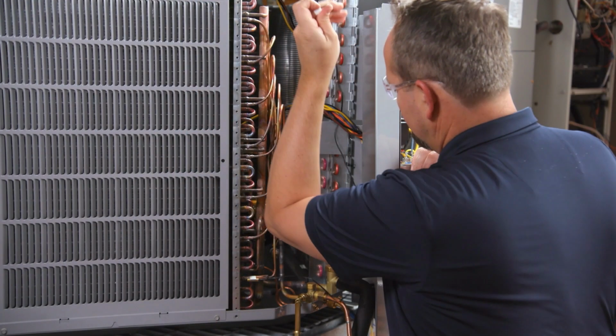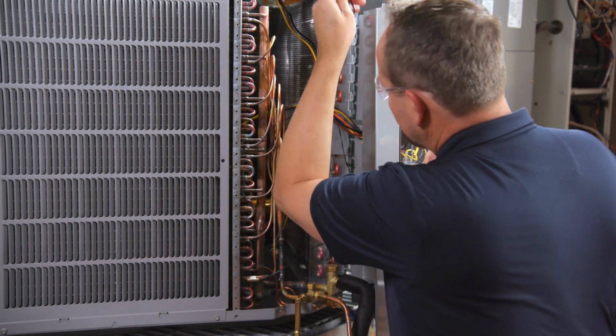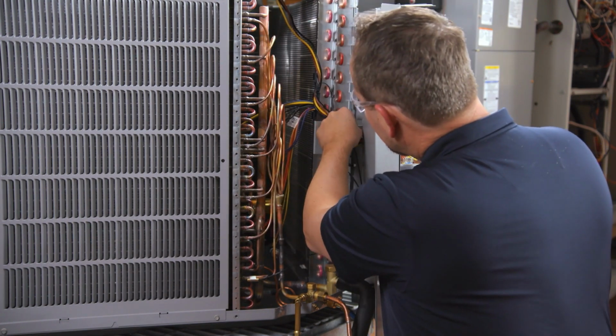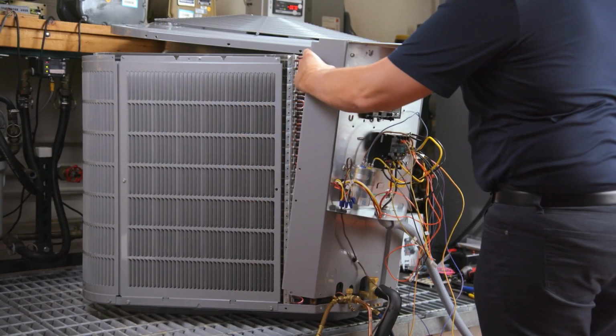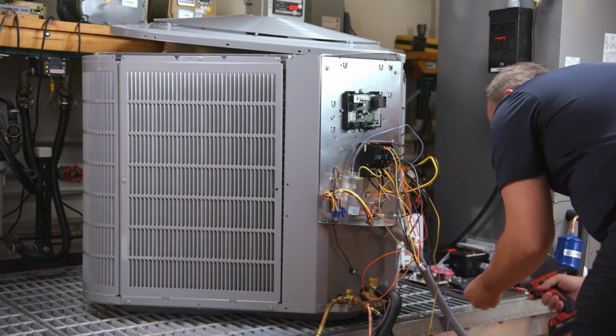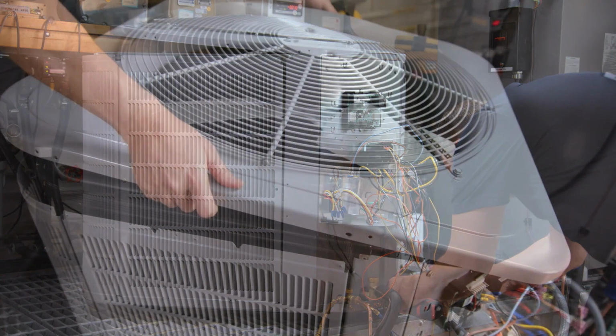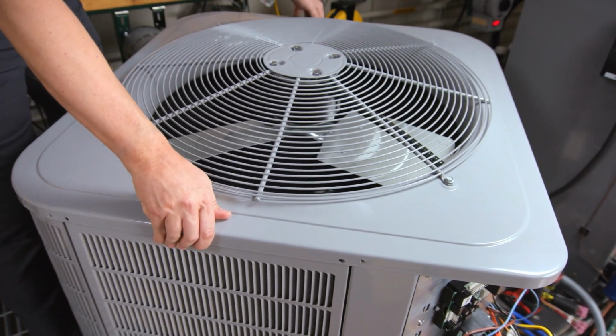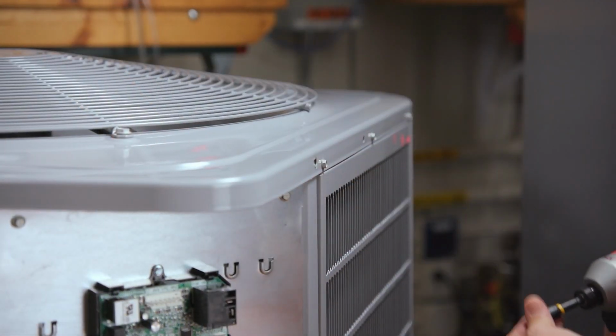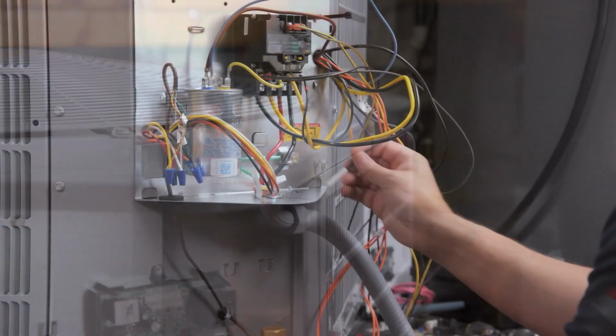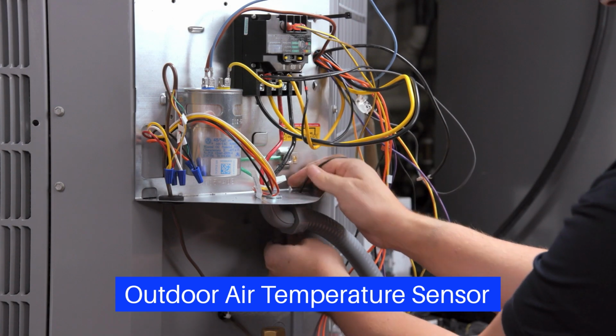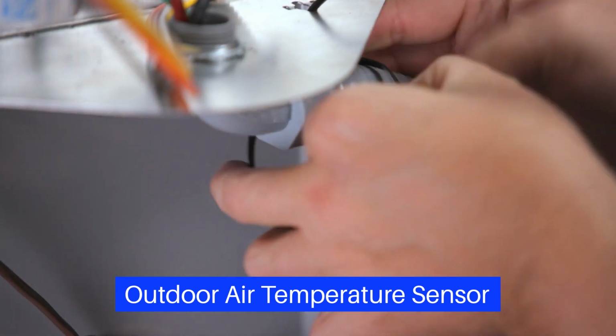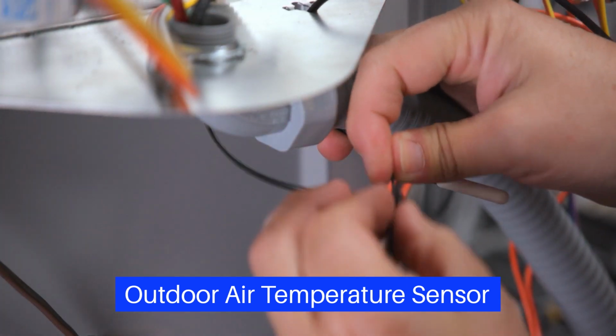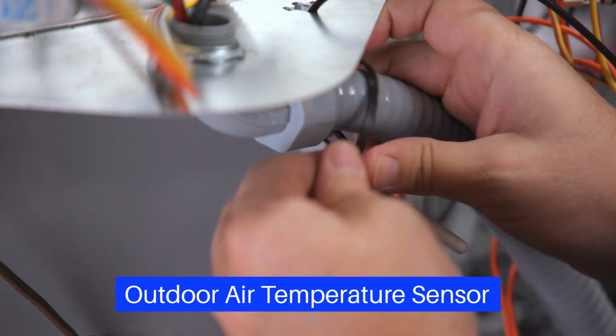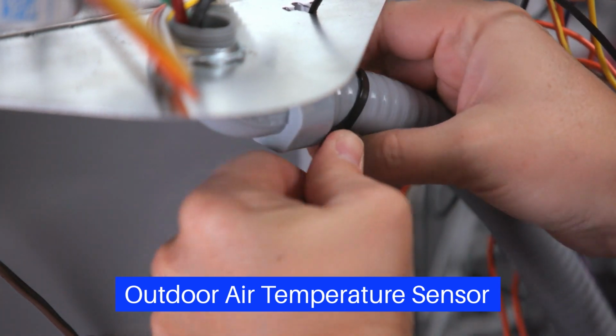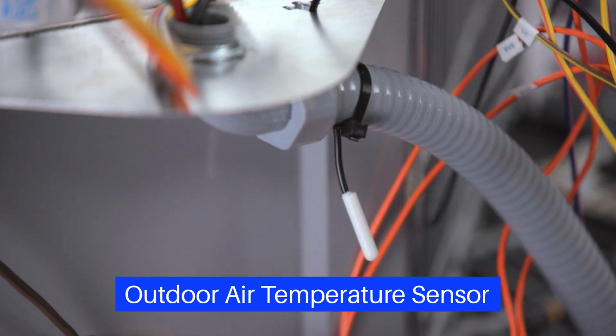Route the wire through the unit. Reattach the control panel and condenser top, making sure wires are away from the condenser fan blades. Secure the condenser top. The outdoor air temperature sensor can be placed wherever suitable to measure the ambient air temperature. In this application, it is installed right outside of the control box. Secure the sensor wire, making sure the sensor is in a safe location and not touching anything.